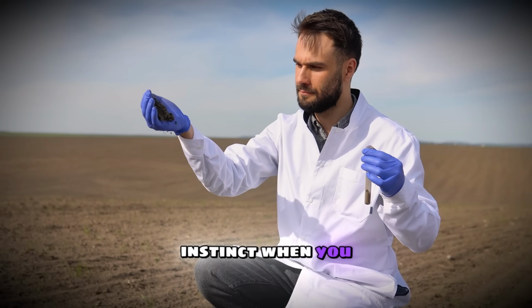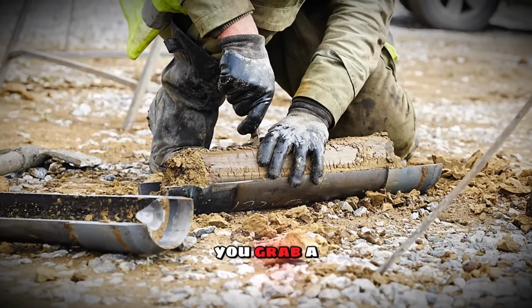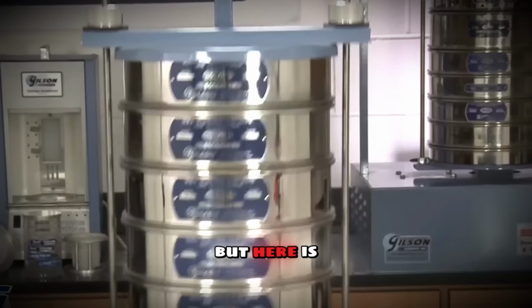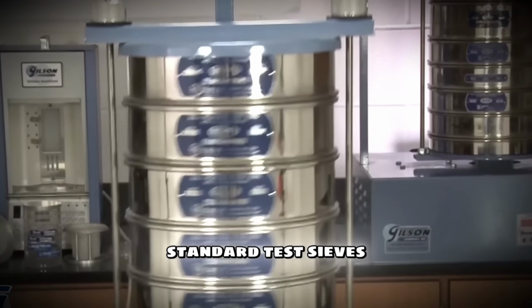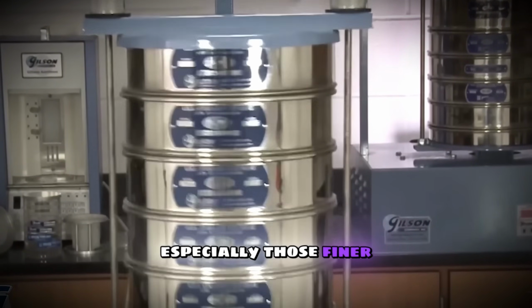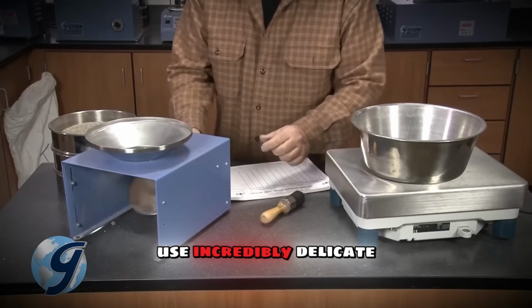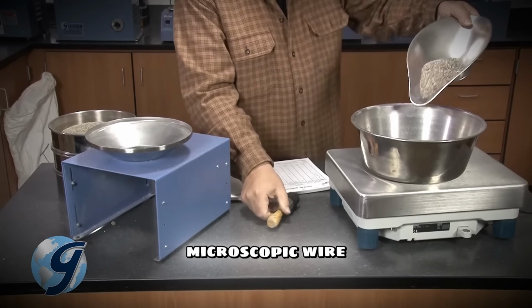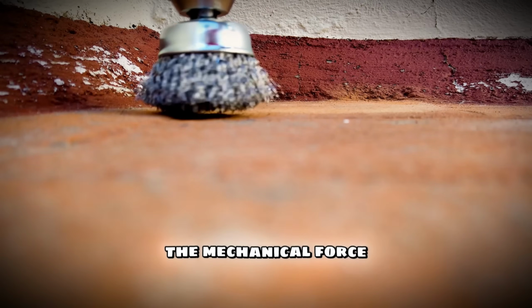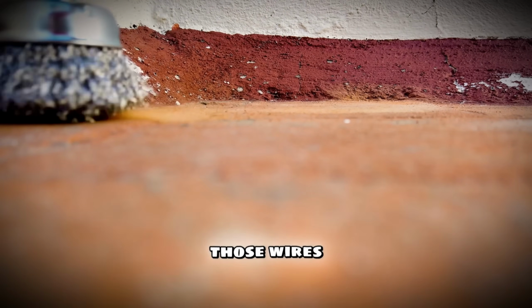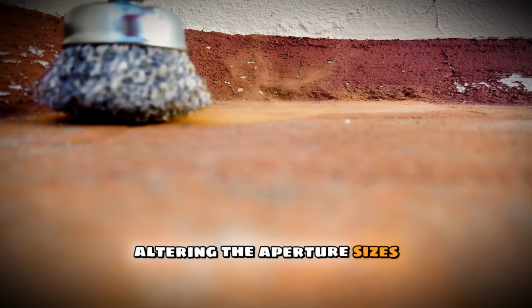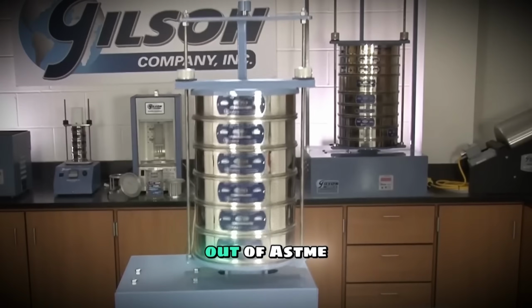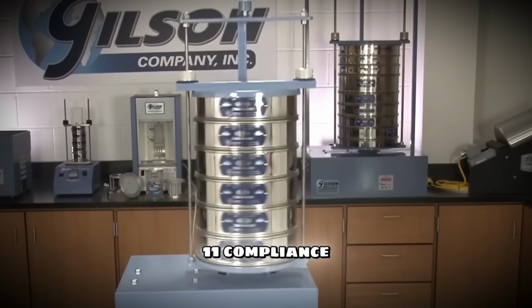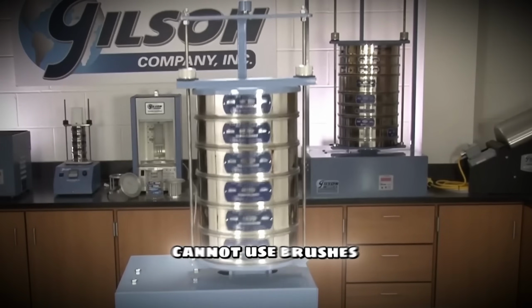What is the natural instinct when you see a blinded sieve? You grab a brush and you start scrubbing. But here is the harsh reality: standard test sieves, especially those finer than a #100 mesh, use incredibly delicate, microscopic wire. When you apply the mechanical force of a brush, you are stretching those wires, altering the aperture sizes, and instantly pulling that sieve out of ASTM E11.